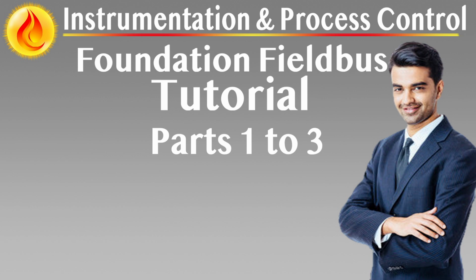A key concept in the communication model is the virtual communication relationship, VCR, which represents logical links between communicating devices or functions. VCRs ensure data is delivered reliably to the intended recipient, whether the model is client-server, bidirectional query response, publisher-subscriber one-to-many periodic updates, or source/sink one-to-many event distribution. Each VCR is uniquely identified within a device and across the network using local indices and global data link addresses.